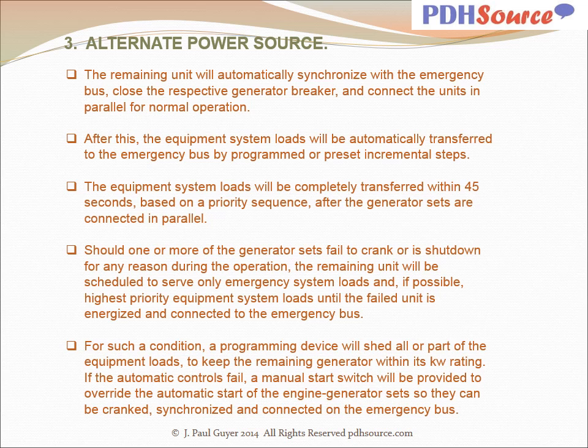Should one or more of the generator sets fail to crank or be shut down for any reason during the operation, the remaining unit will be scheduled to serve only emergency system loads and, if possible, highest priority equipment system loads until the failed unit is energized and connected to the emergency bus. For such a condition, a programming device will shed all or part of the equipment loads to keep the remaining generator within its kW rating. If the automatic controls fail, a manual start switch will be provided to override the automatic start of the engine generator sets so that they can be cranked, synchronized, and connected on the emergency bus.